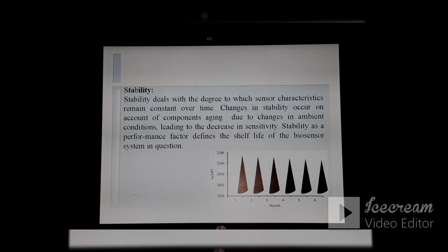Here, one example is shown. Per month, some tests are conducted for the same sensor, and the corresponding outputs are recorded, and per month curves are drawn. Here, up to 6 months, the sensor has shown similar results. Under such circumstances, we can say that the sensor is stable for 6 months. That is, its lifetime or shelf life is 180 days.